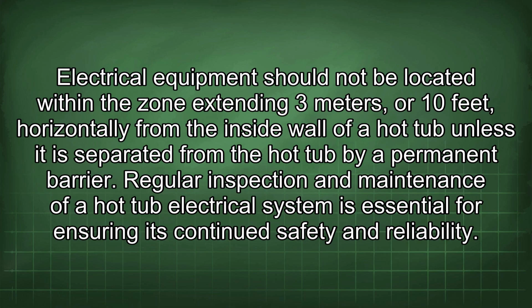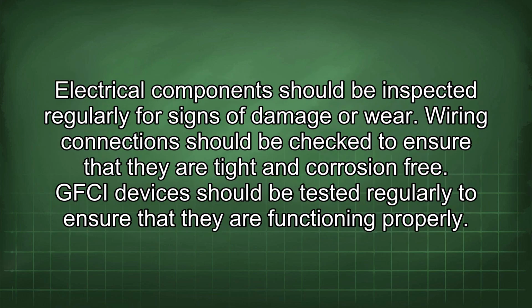Electrical equipment should not be located within the zone extending 3 meters, or 10 feet, horizontally from the inside wall of a hot tub unless it is separated from the hot tub by a permanent barrier. Regular inspection and maintenance of a hot tub electrical system is essential for ensuring its continued safety and reliability. The electrical components should be inspected regularly for signs of damage or wear. Wiring connections should be checked to ensure that they are tight and corrosion-free. GFCI devices should be tested regularly to ensure that they are functioning properly.